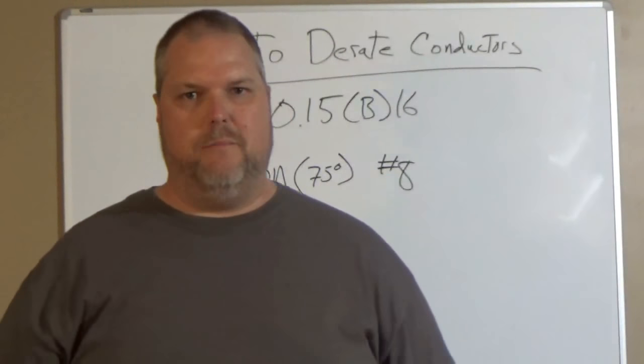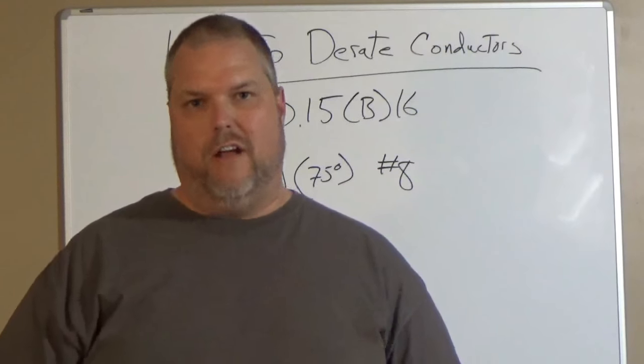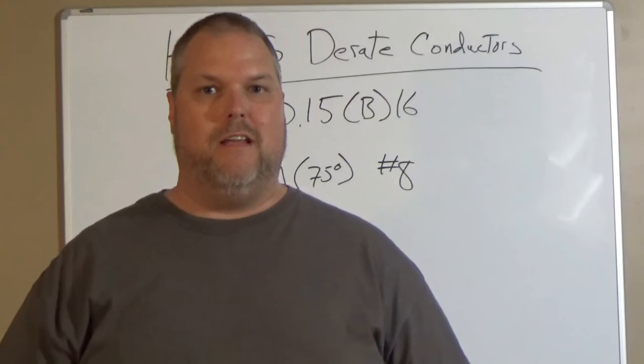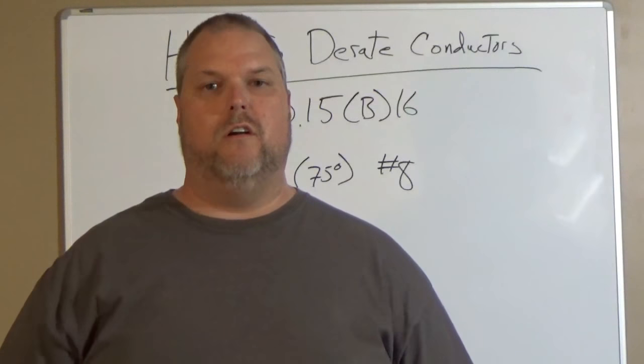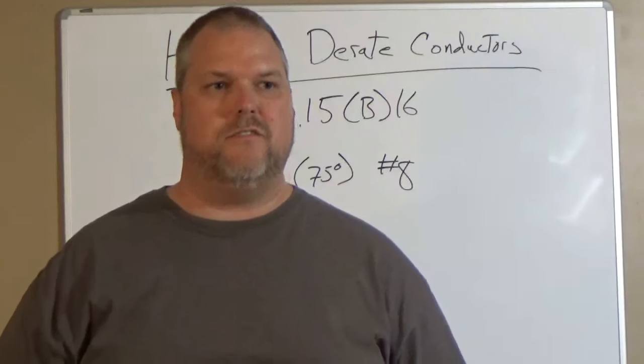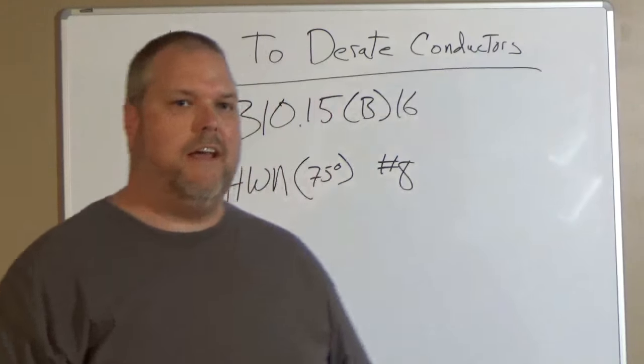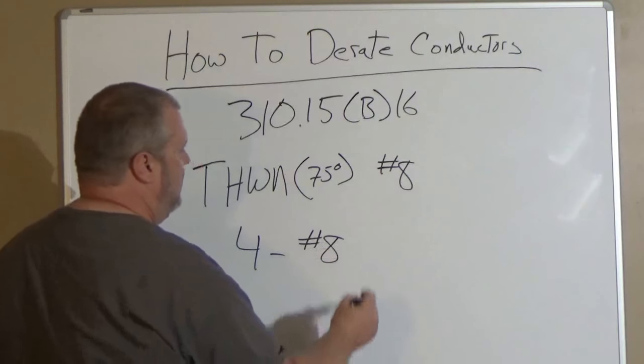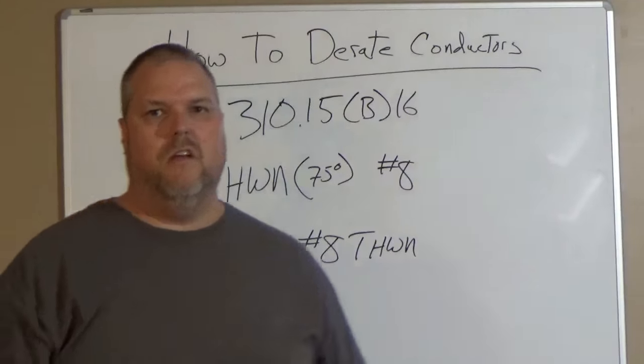Now insulation type is important. You have to understand whatever type insulation you're installing, your amperages are going to change a little bit. So make sure you understand the difference between THHN and THWN and what they're used for. Maybe we'll explain this in another video—always love new ideas. So let's look at this. If I have four conductors in a conduit, so I'm taking four number 8 THWN wires.